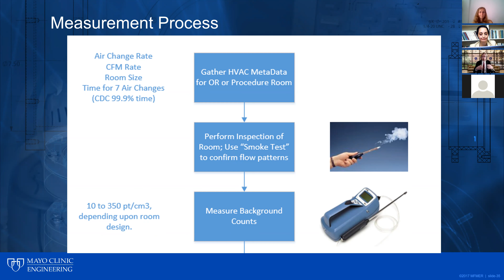How we basically did that, we started by doing something called a smoke test. So we would go into the room and release a puff of smoke, and then we would measure the background counts. The reason we were doing that is we wanted to move around the room and find out if there were dead spots. The fear was that this aerosol would collect in areas of the room and wouldn't be effectively cleared by the room ventilation. So that was the first thing we looked at. And then we did the aerosol challenge.